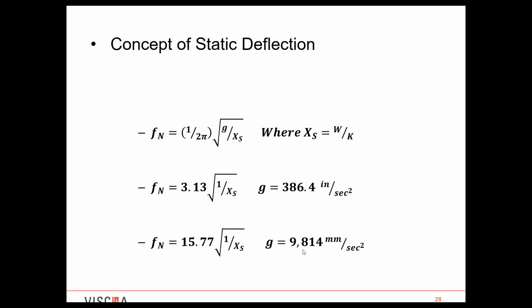And then finally, from my university days, I tend to think of gravity as 9.82 meters per second squared, but of course that is also 9,814 millimeters per second squared. You can think of it in terms of that gravity if you wish, with 15.77 times the square root of 1 over your static deflection. I hope this is giving you some definitions and ideas of how we look at vibration isolation efficiency, the transmissibility, and a little bit about the damping, although John is very correct that typically in our industry we can't count on damping. Unless it's specifically designed, we presume that the damping ratio is 0. At this point, I'm going to turn it back over to John, and he is going to give you some good ideas of what not to do, and hopefully what to do.